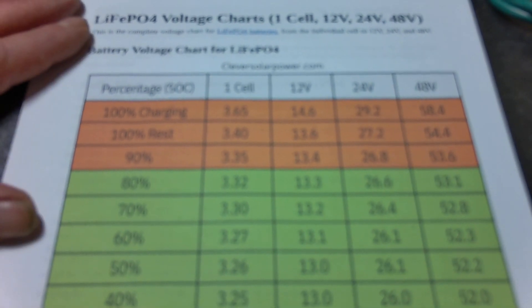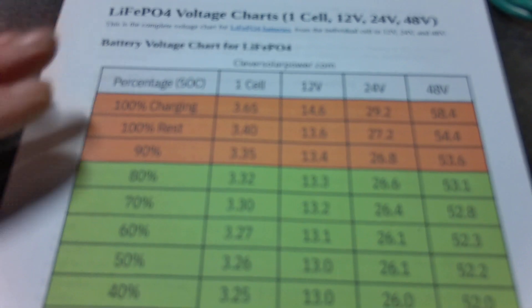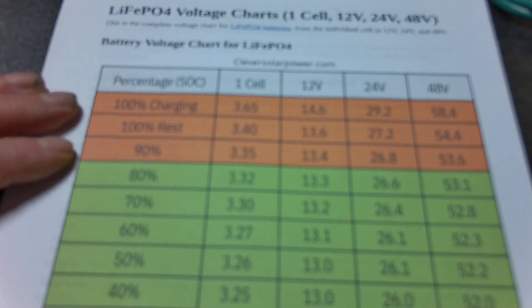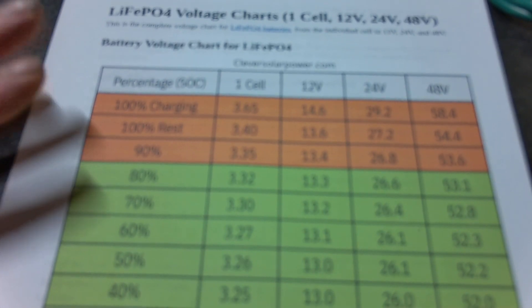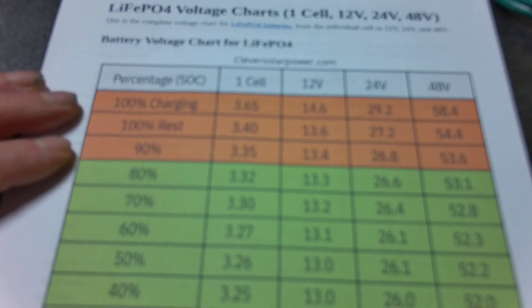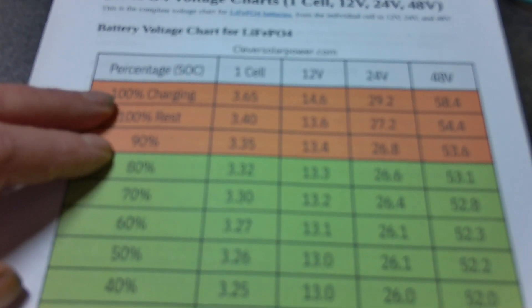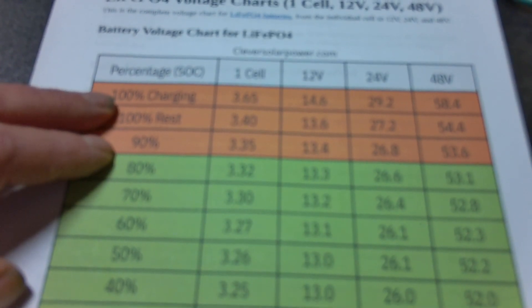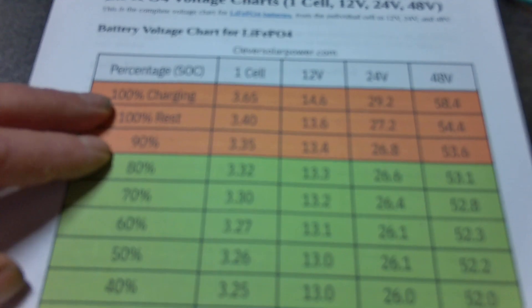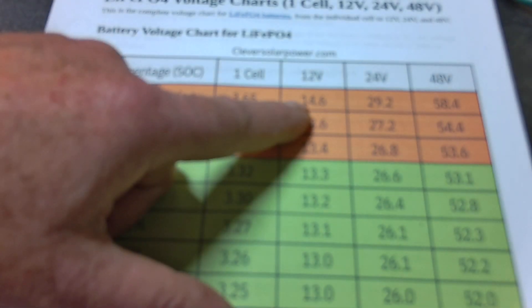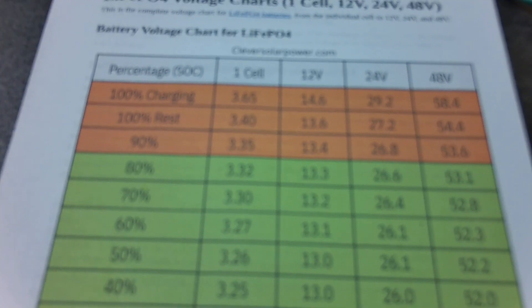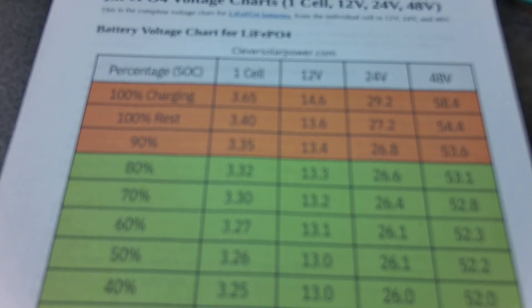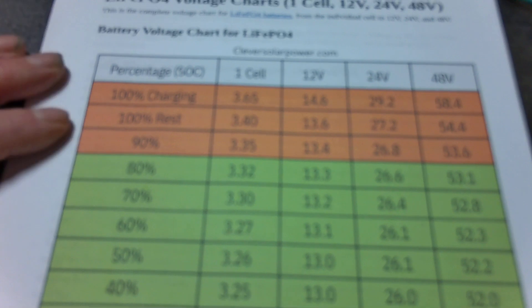But what I'll say is that when you first get a battery, you need to equalize the cells. So you need to charge your battery up to 100 percent, and the battery has to get up to 14.6, and your battery management system in the battery should shut it down after it's fully charged.